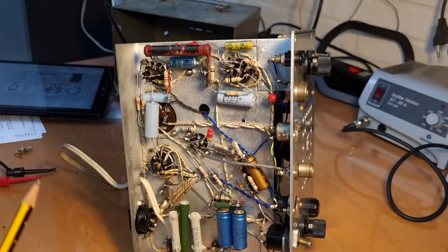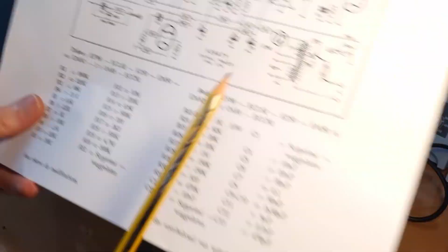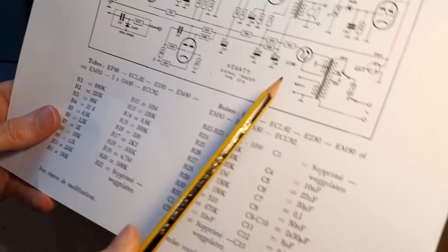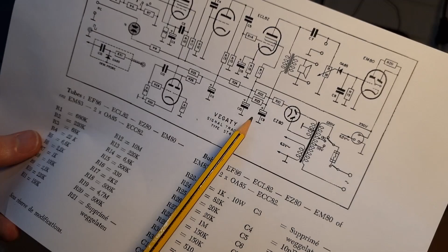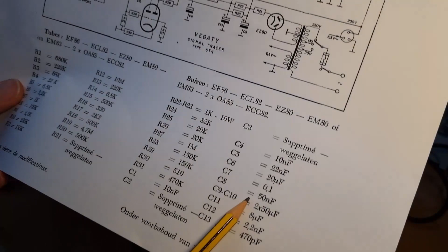So, okay, just as I expected, in test equipment often all the tubes are still really good, because test equipment is not used as extensively as a radio or any audio gear. It's not running constantly, it's only being used for very short time periods compared to a radio, which plays for hundreds or thousands of hours. So most of the time the tubes in test equipment, if they are working, are still really strong, and that's also what we see here. These tubes are perfectly fine.